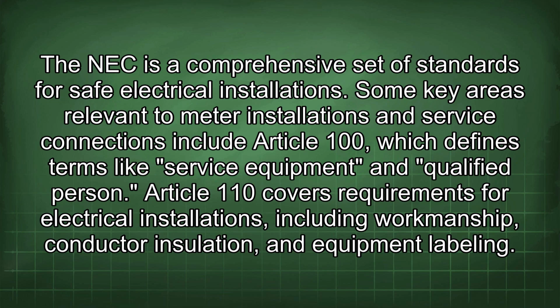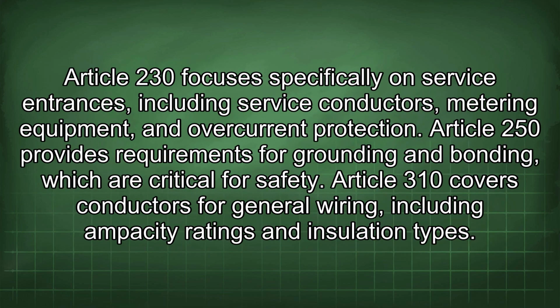Some key areas relevant to meter installations and service connections include Article 100, which defines terms like service equipment and qualified person. Article 110 covers requirements for electrical installations, including workmanship, conductor installation, and equipment labeling. Article 230 focuses specifically on service entrances, including service conductors, metering equipment, and overcurrent protection.